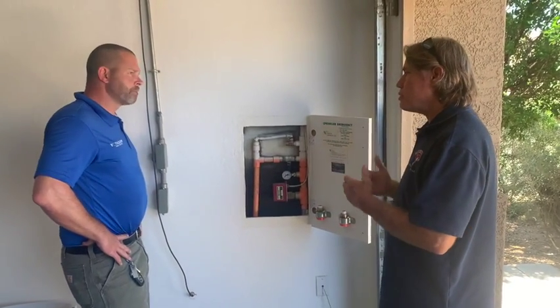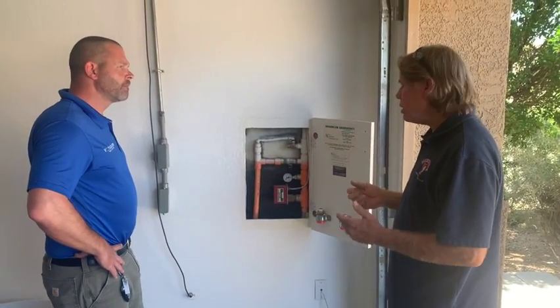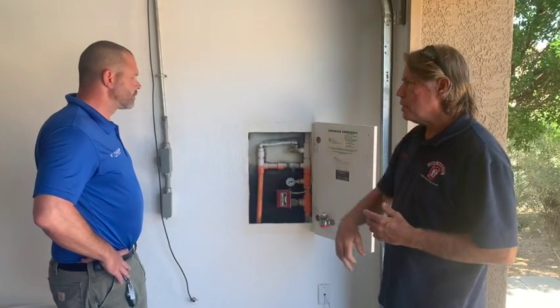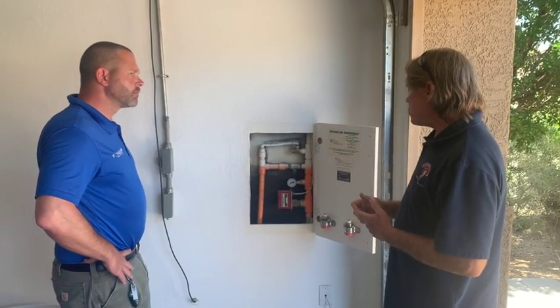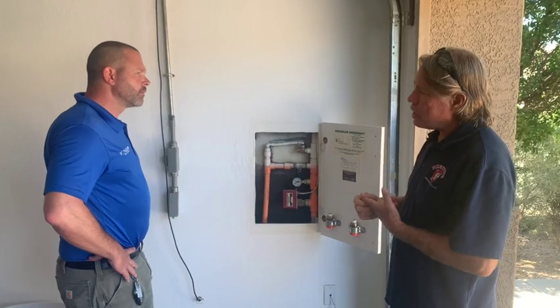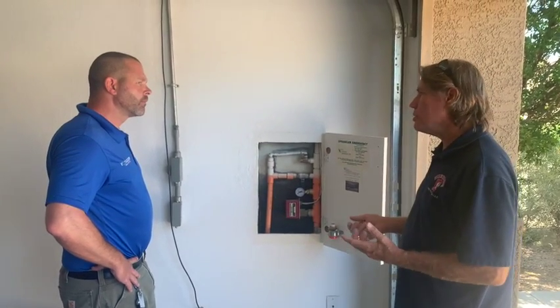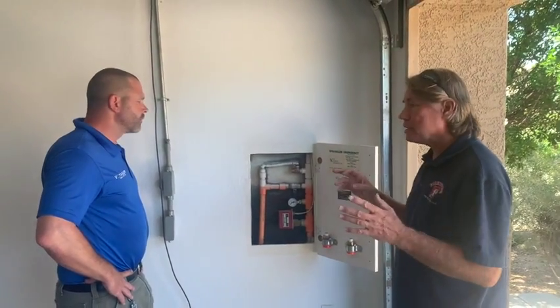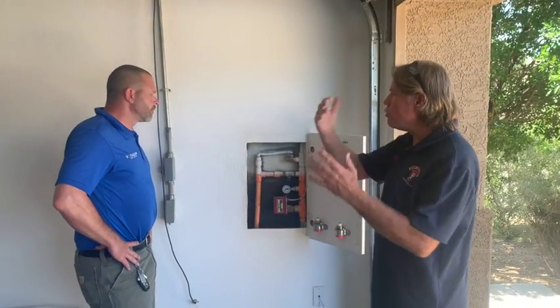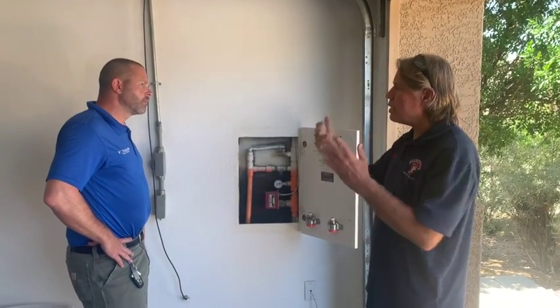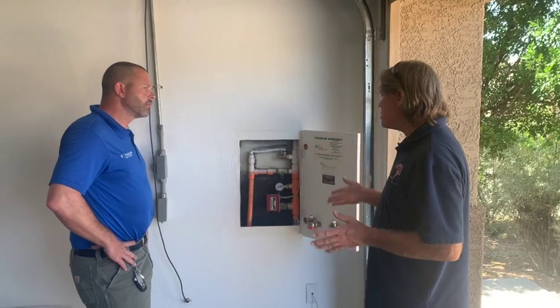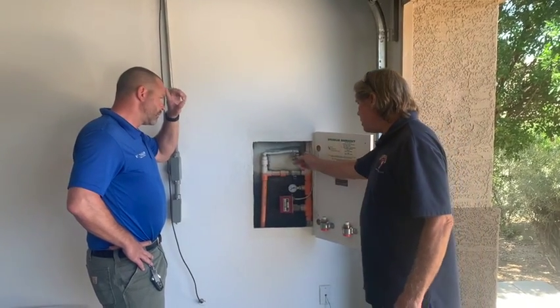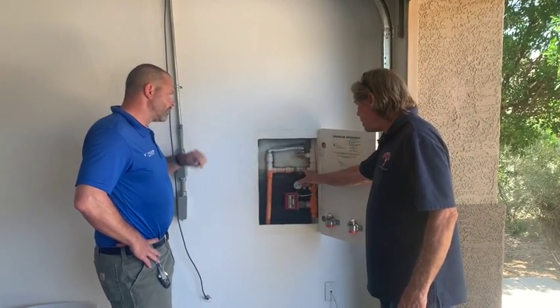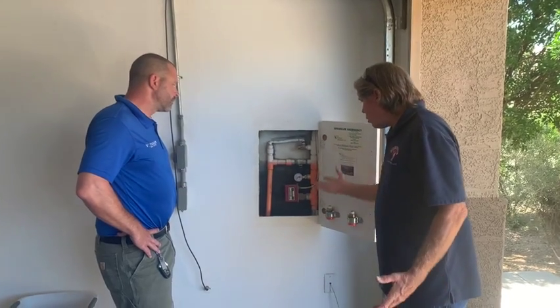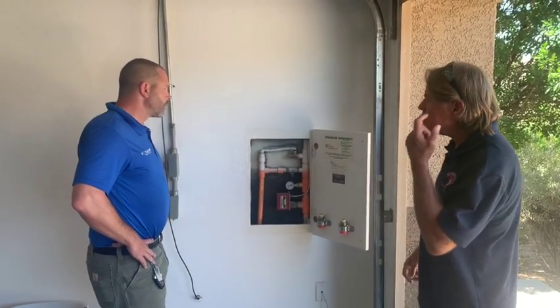So the maintenance aspect of this, once or twice a year, is to flush the system. Especially in Arizona, we have a lot of particulates, calcification, and microorganisms in the water, and they go after any metal they can find. So if you move that water through the system on a regular basis, you're going to decrease the chances of having things fail like your PRV, the main drain valve, or other components in the system.